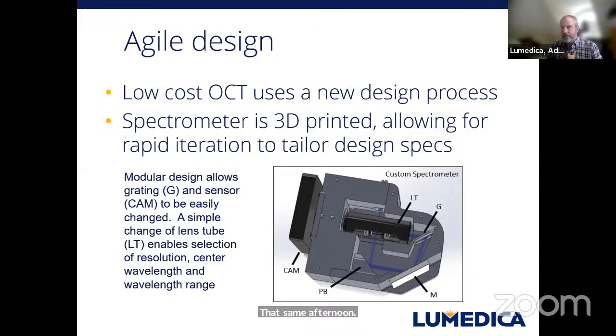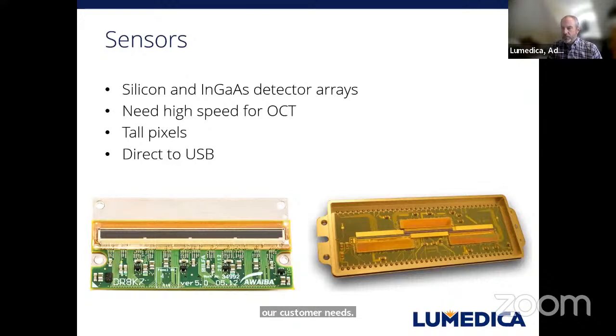And what would I like to see from the field? We use silicon and InGaAs detector arrays in our spectrometers. There's only a few of them that are available for high speed, with the high speed that's needed for OCT. Usually in a spectrometer, you're integrating for a long time, but the OCT spectrometers need to go fast. Our initial version was 13 kilohertz, but now you saw I have one for 34 kilohertz, all the way up to 80 kilohertz. If we had really fast OCT spectrometers with the unique design of a tall pixel, so typically 200 microns by 10, it would give us ability to innovate even further in the field.